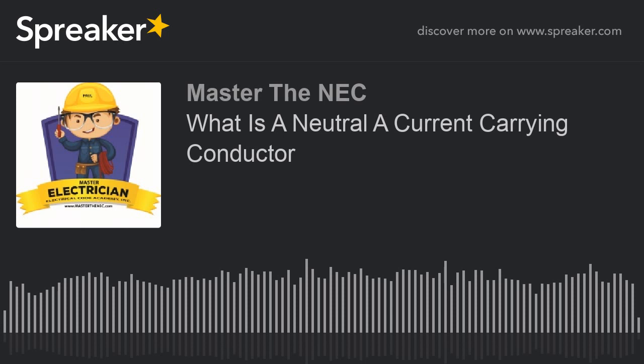Now, there's some things that you can do in the design stage that I tell people. There's many things you can do. For example, I could have what's called a K-type or K-rated transformer that will basically try to cancel out these frequencies or reduce them, because, again, the amount of current in the waveform, it becomes a frequency issue, and again, above our discussion today. But just remember that we don't have that effective cancellation of neutral current. It becomes erratic, and because that cancellation doesn't take place, it almost becomes additive, if you will, the easy way to explain it. And this is something that the design engineers have to take into consideration. They really need to know.